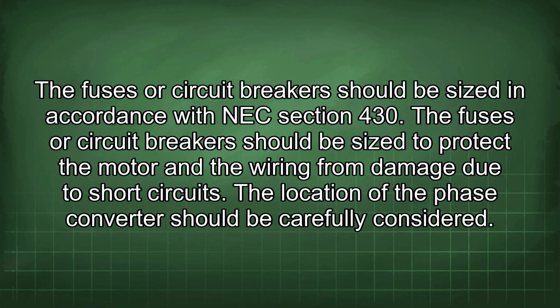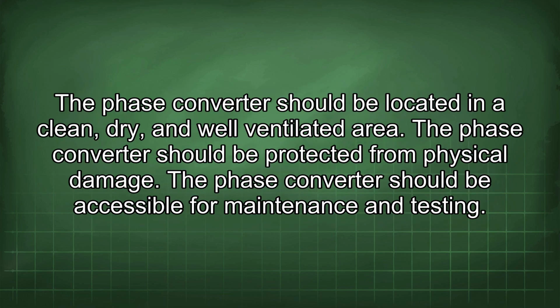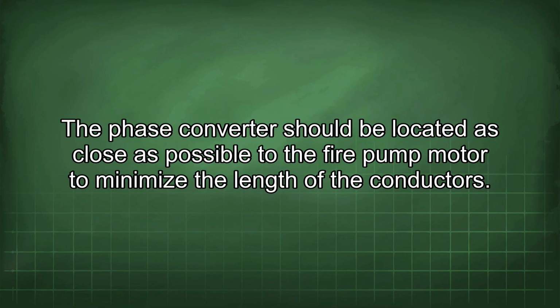The location of the phase converter should be carefully considered. The phase converter should be located in a clean, dry, and well-ventilated area. The phase converter should be protected from physical damage. The phase converter should be accessible for maintenance and testing. The phase converter should be located as close as possible to the fire pump motor to minimize the length of the conductors.